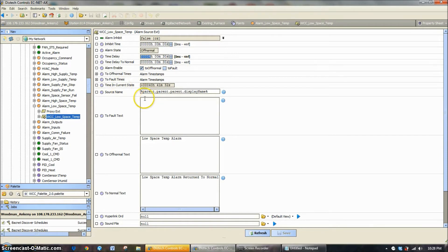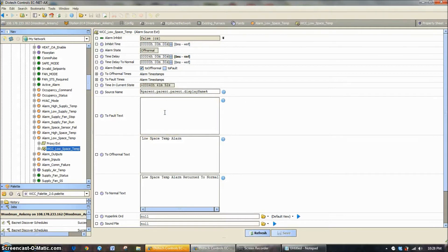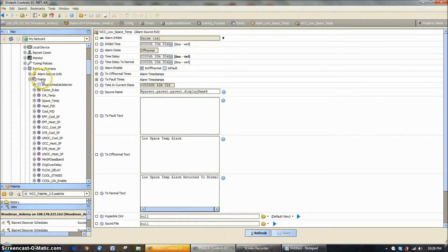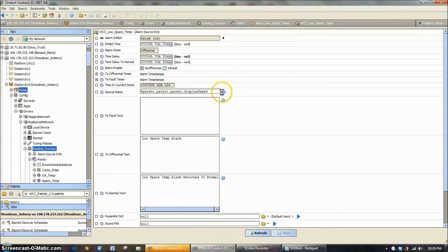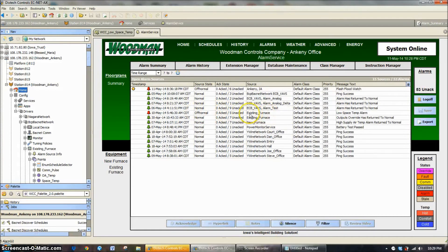Source name is one that seems to cause a lot of confusion. It's just a short way of writing out an actual name. So if I wanted to make my source name 'Furnace' or 'Ryan's Office', I could just type that in. But imagine big systems with hundreds of zones — that's a pretty inefficient way to do it. So using parent.parent.parent.displayName, since the alarm extension is here on the low space temp point, parent one, parent two, parent three — I want the display name for that. Since I use this little bit of code, it's going to come out and say 'existing furnace.' So when we go back and look at our alarms, that's why we see 'existing furnace' right there — because of the parent.parent.parent, and that's what's showing the source for that alarm.